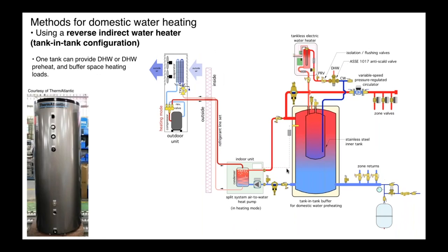So one more option here. You'll see this more in Europe, although this tank that I'm showing you here from ThermAtlantic is available in North America. This is a tank-in-tank configuration. We have a buffer tank, which is the outer tank here, and suspended within that, in this case, it's a 40-gallon stainless steel inner tank. And you see the idea here is that your cold domestic water just goes into that tank, and that inner 40-gallon tank is suspended in and completely surrounded by heated water. So it's going to have heat transfer through the walls.